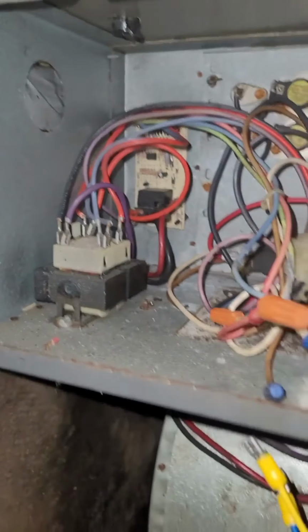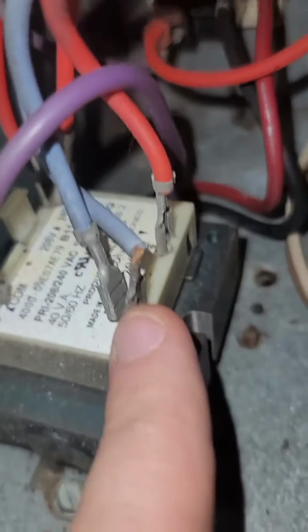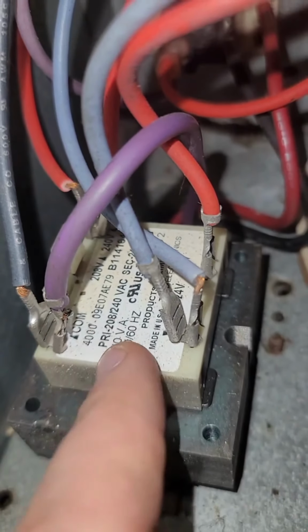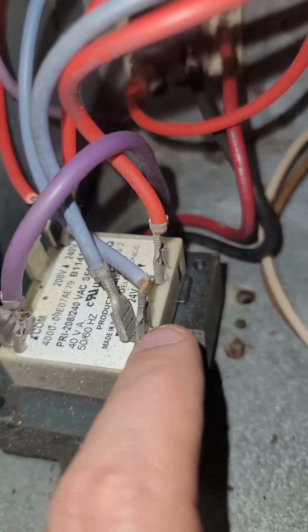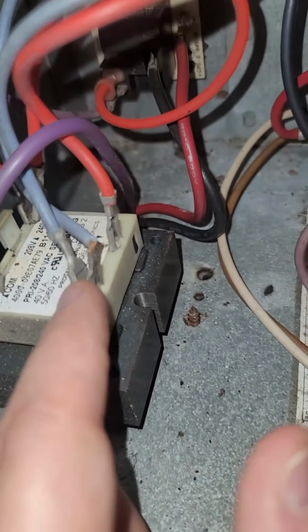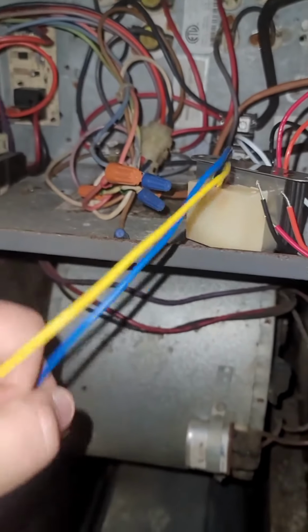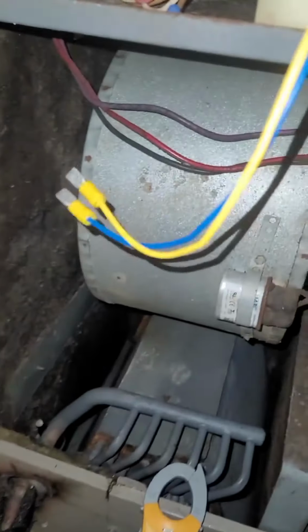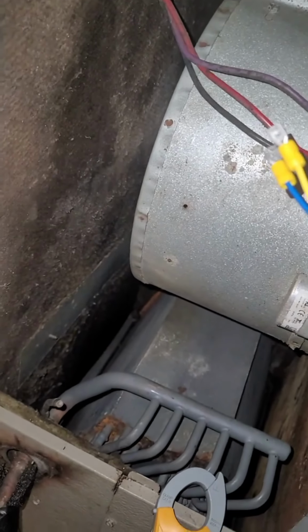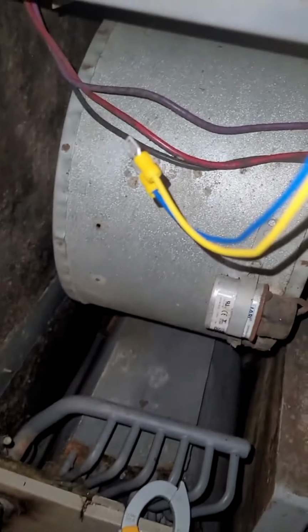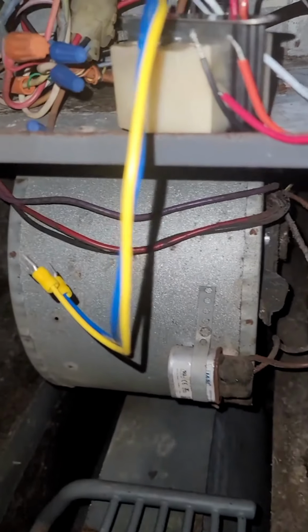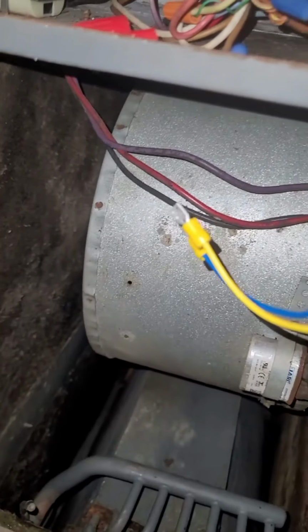As you can also see, these have electrical connectors on them and the other ones do not. You can see the common and the 208 and 240 hookups on this particular transformer. And I'm going to show you how we're going to go about changing that. See, I put these little electrical connectors on it, so that way I can put an inline fuse, so that way if we have any other issues, we can just change fuses out, which is a lot less to deal with than changing an actual transformer.